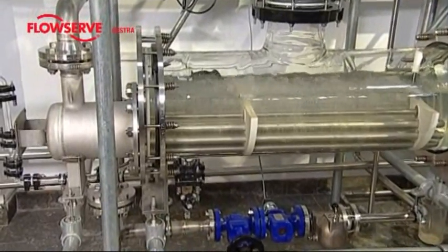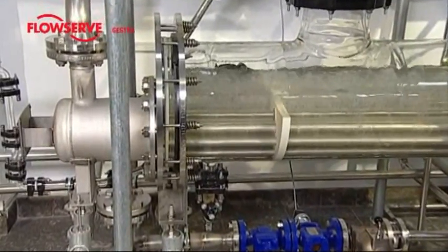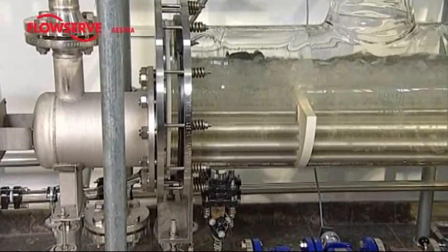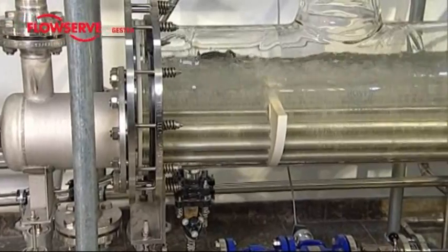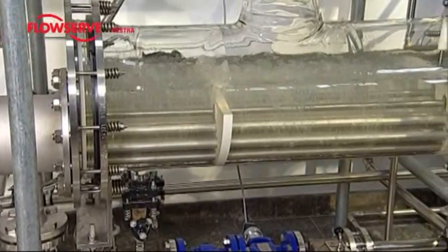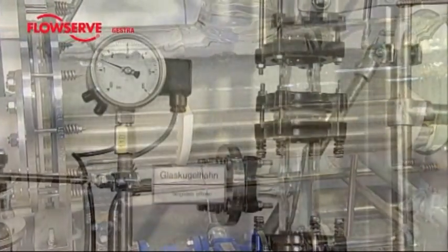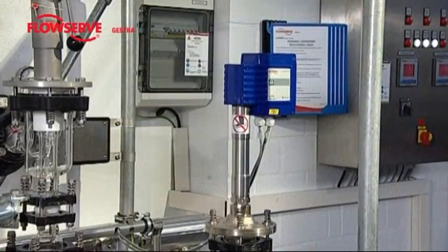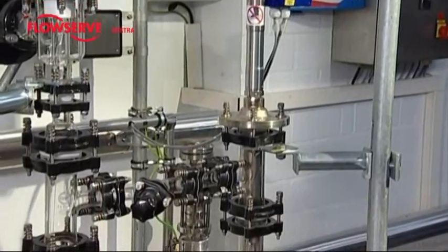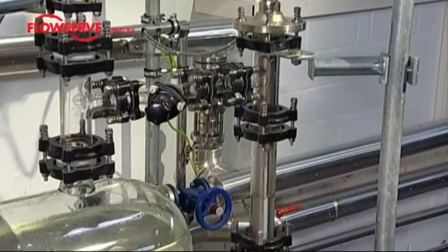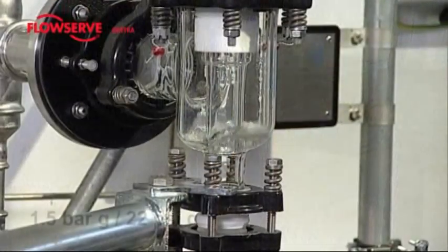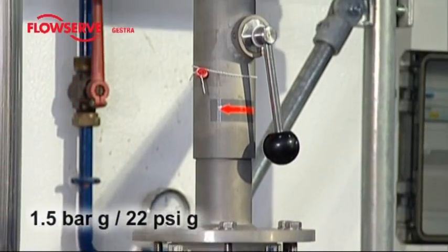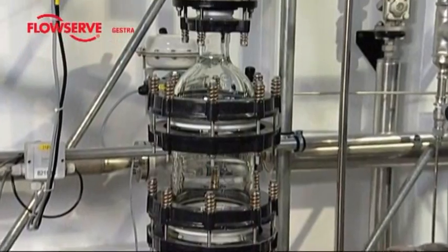The steam generator consists of the following components: the horizontal evaporator with a stainless steel head for the primary steam inlet and condensate outlet, as well as 16 evaporator tubes. A pressure gauge with pressure transducer and a level measurement unit employing the capacitive measurement principle in an external measuring pot. A safety valve with a blow-off pressure at 1.5 bar gauge, and a steam outlet with a ball valve made of glass.